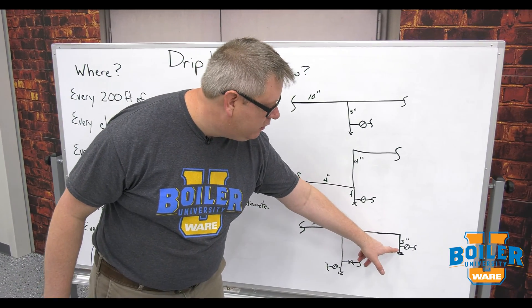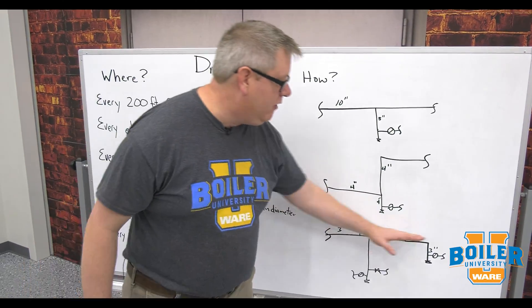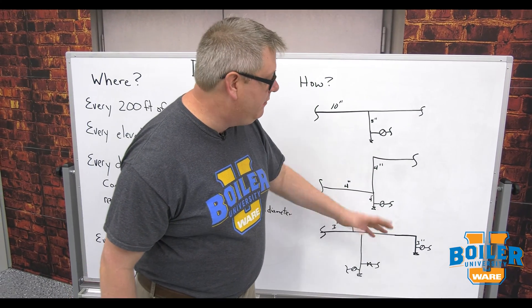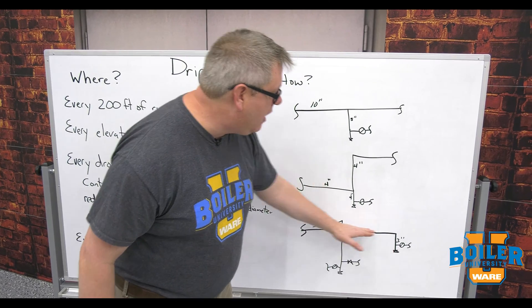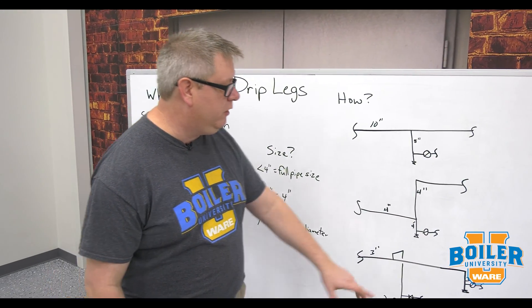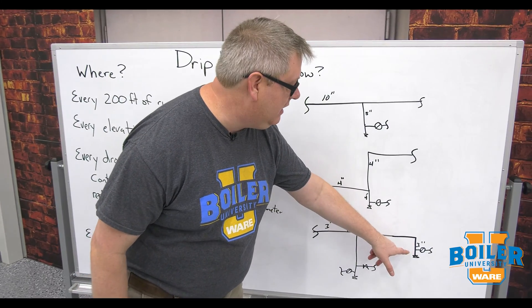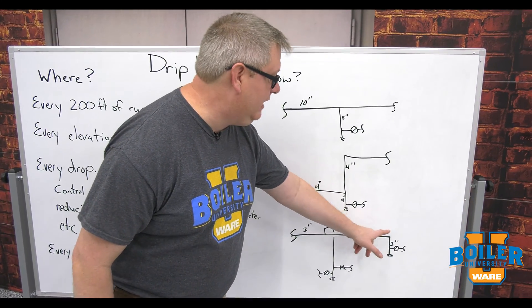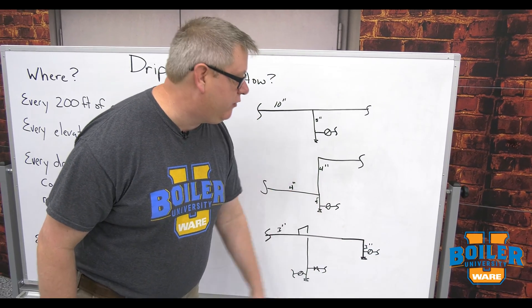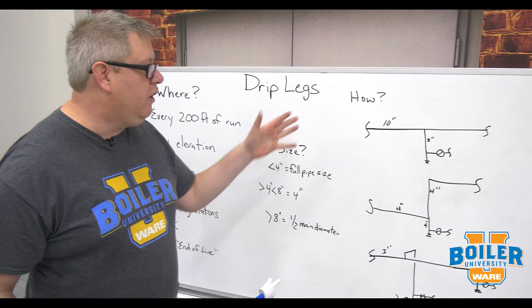And here we also show our end of main drip leg. So that main running down to the end of the plant—maybe we're going to add something down there later, it doesn't matter—we can't allow condensate to accumulate in there. It's going to cause problems and corrosion. So we'll drop with a 90. If we want to, we can use a T and put an air vent on there. Come out the side to our trap.